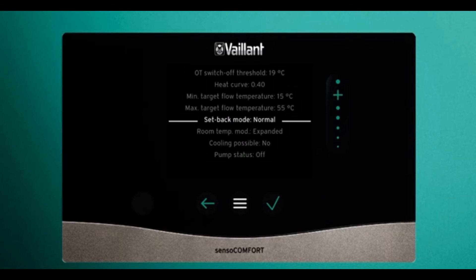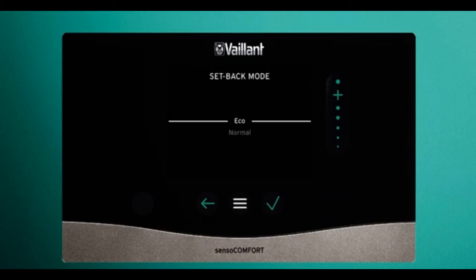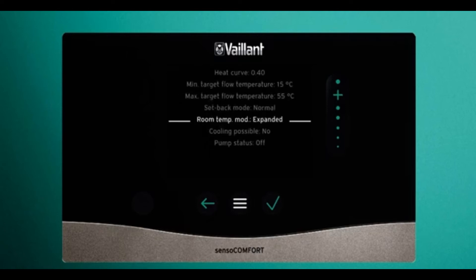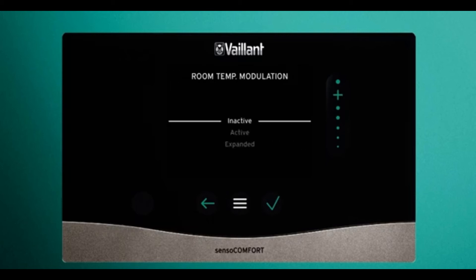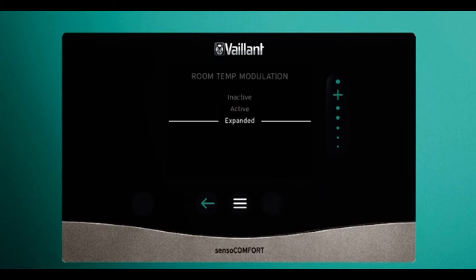Setback mode should be set as normal if you're using the sensoCOMFORT as a room thermostat. If it is set to eco, it will be in frost protection mode outside of the times you've programmed to heat. Room temp mode has three options: inactive, which uses pure weather compensation with no room influence; active, which adjusts the flow based on the current room temperature; and expanded, which is how it is set as a room thermostat — allowing you to use the sensoCOMFORT as a room thermostat with weather compensation.